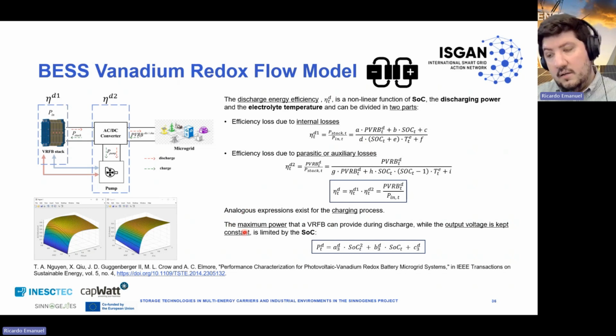Another important fundamental dynamic is that the maximum power the battery can provide, while keeping output voltage constant, is limited by the SOC. This is an important assumption since we provide set points for 15 minutes, the minimum time step and granularity we consider, so we can say the output voltage is relatively constant in that period.